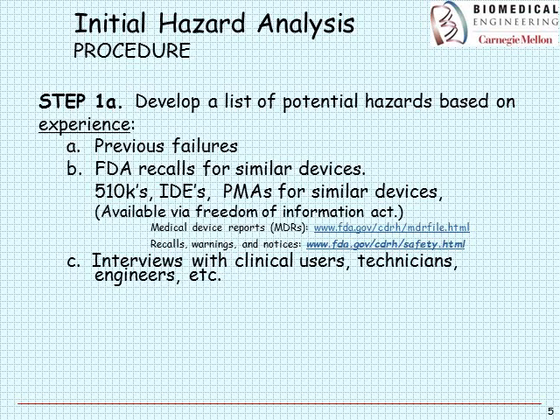The first step takes place early in the design process, around the same time you're creating user requirements. It involves developing a list of potential hazards. Initially, we create this list based on experience — for example, our experience with previous failures, or specific failures recorded by the FDA for similar devices. There are resources available through the Freedom of Information Act. We can also proactively create a list based on interviews with people experienced in that environment and technology.